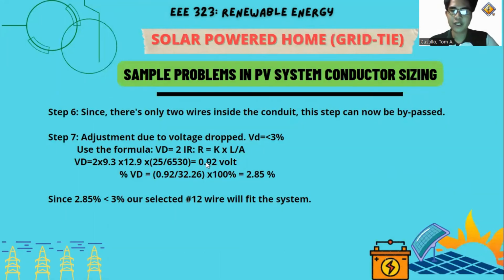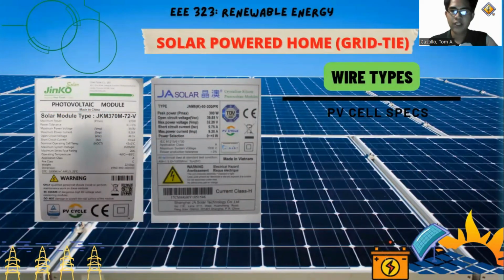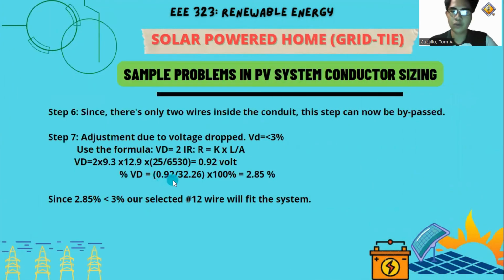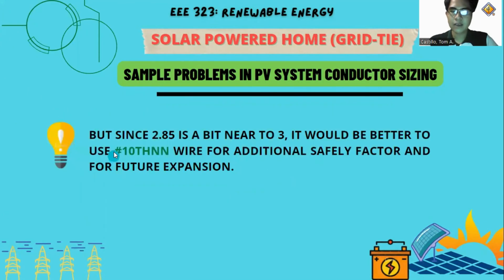So, ngayon, paano natin malalaman yung percent ng voltage drop? So, yung 0.92 volts na voltage drop natin, i-divide natin sa maximum power voltage, then times 100%. So, ano ba yung maximum power voltage natin? So, based on the specs, yung maximum power voltage is 32.26 volts. So, 0.92 divided by 32.26 times 100%, ang percent ng voltage drop natin is 2.85%. Since 2.85% is less than 3%, our selected number 12 wire will fit the system. But, since 2.85 is a bit near to 3, it will be better to use number 10 THHN wire for additional safety factor and for future expansion.